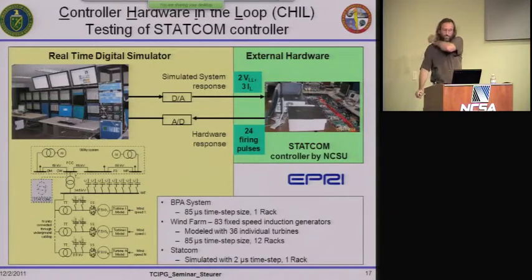One project we had a couple of years ago was done jointly with DOE and EPRI. We received a static synchronous compensator (STATCOM) controller that utilized a 5-level topology of switches to compensate reactive power at a wind farm on the BPA system. Before going into the field, this controller was sent to us to connect to a simulated wind farm, the rest of the system, and the StatCom power stage.